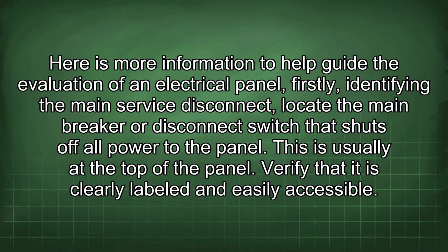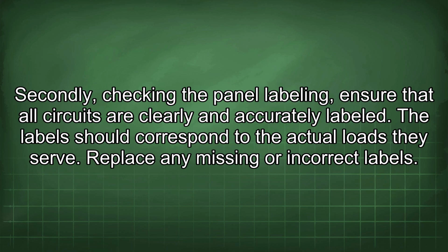Firstly, identifying the main service disconnect. Locate the main breaker or disconnect switch that shuts off all power to the panel. This is usually at the top of the panel. Verify that it is clearly labeled and easily accessible. Secondly, checking the panel labeling. Ensure that all circuits are clearly and accurately labeled. The labels should correspond to the actual loads they serve. Replace any missing or incorrect labels.